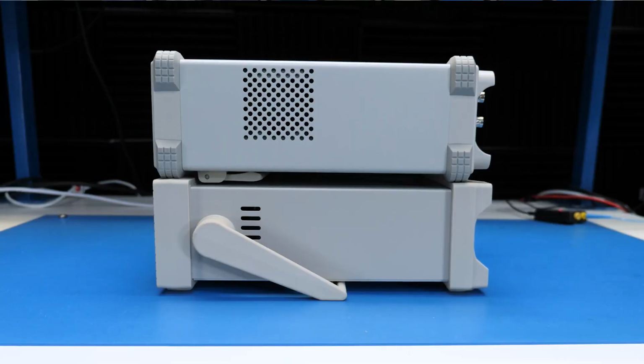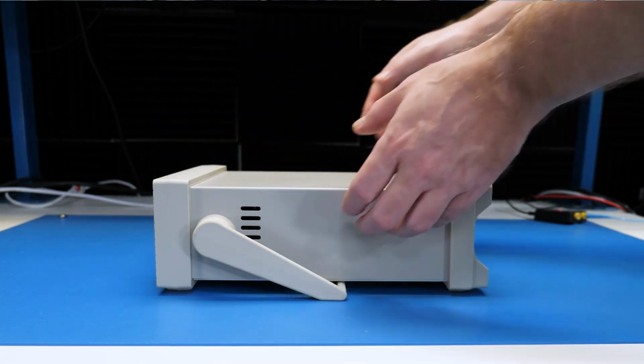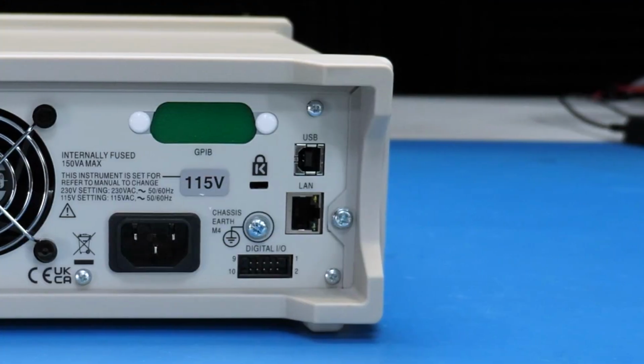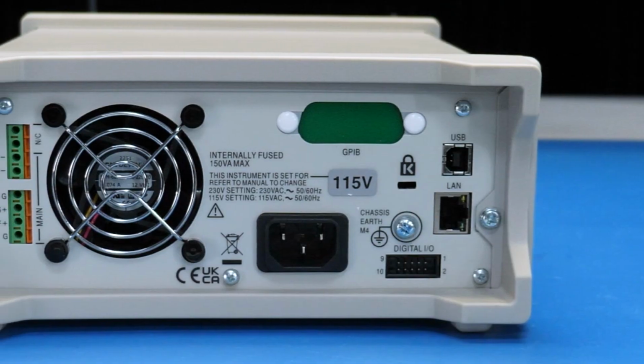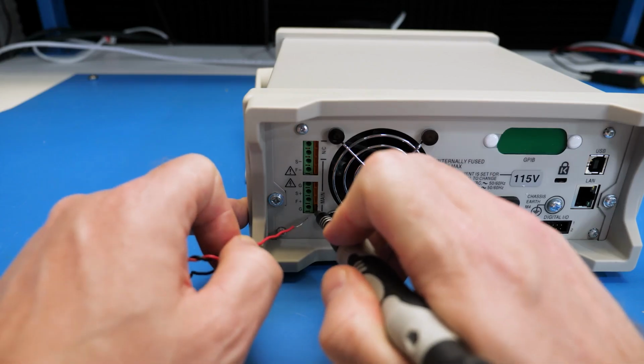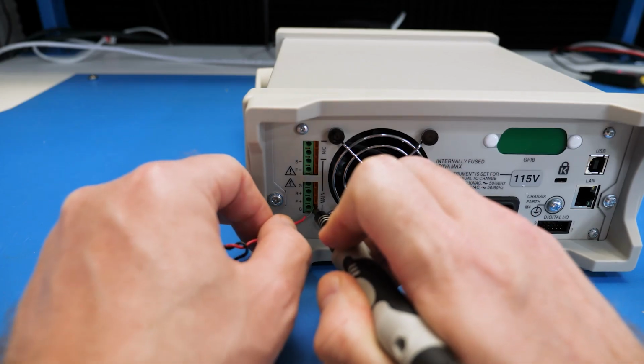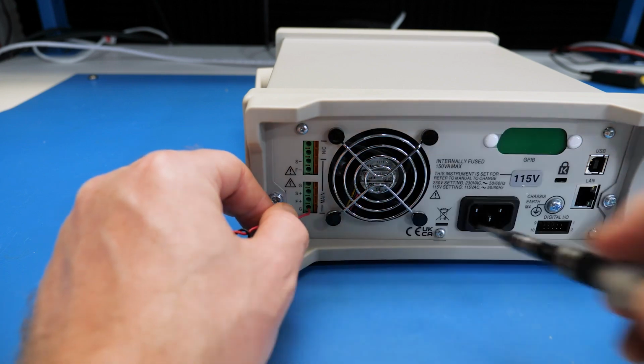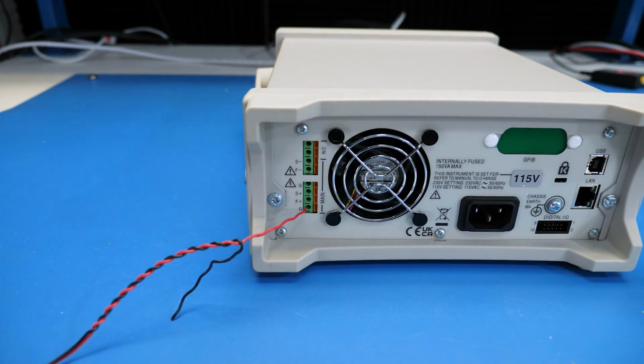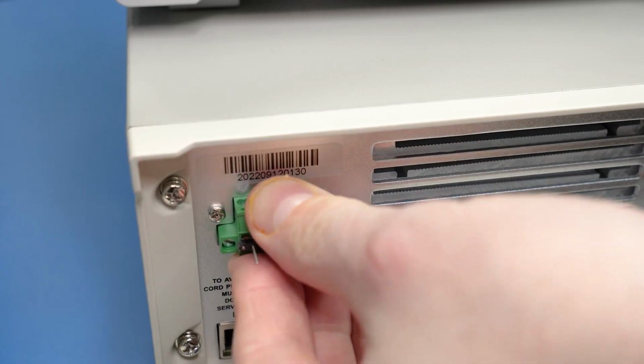This unit is incredibly compact. It is the same size as a benchtop multimeter or switching bench power supply. On the back are ports for remote access, a digital I/O port, and rear terminals. What I really like is that these terminals have a built-in push and release mechanism. It does take a little bit of force, but my other instruments all use a two-piece adapter, which is easy to lose. Ask me how I know.